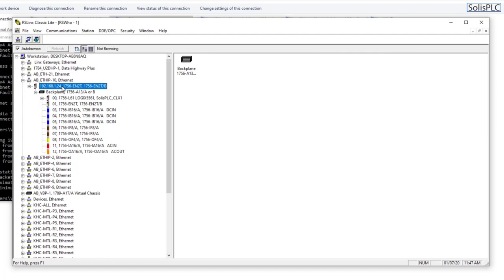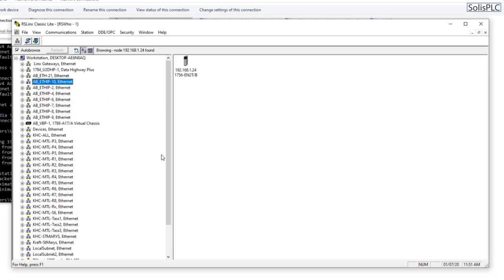And we've set a new IP address for the card. We've reset it through DIP switches. But let's look at the other method. So I'm just going to connect a USB cable to the front of that card, and we're going to be exploring the same connection through USB. Okay, so the USB is plugged in, and usually what happens in RSLinx is that it detects the connection automatically.